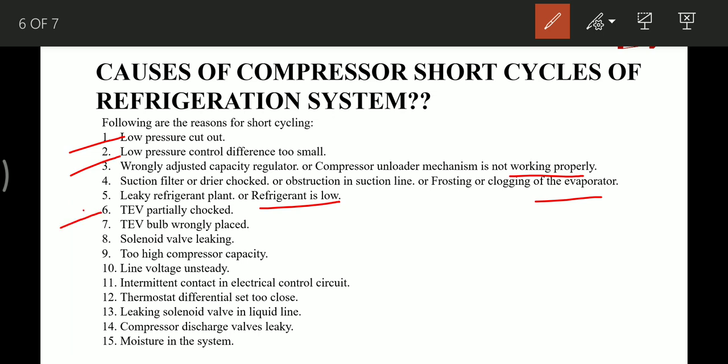Other reasons are solenoid valve leaky, compressor capacity may be too high, and line voltage unsteady, meaning fluctuation in the line voltage.